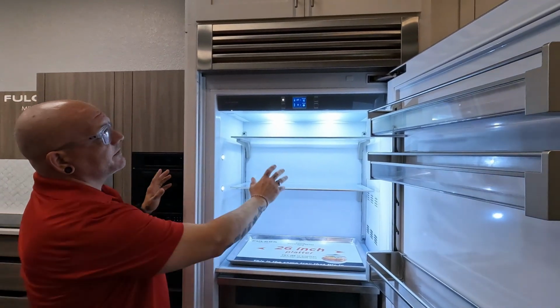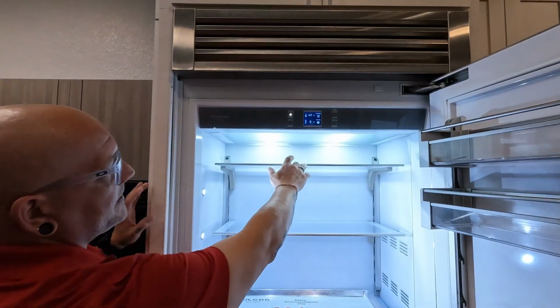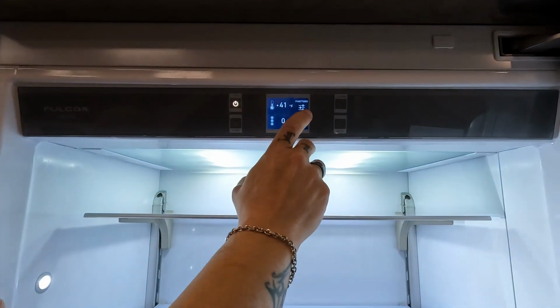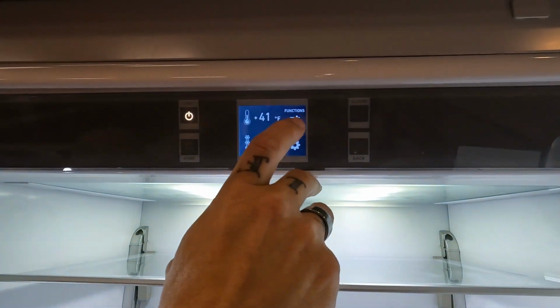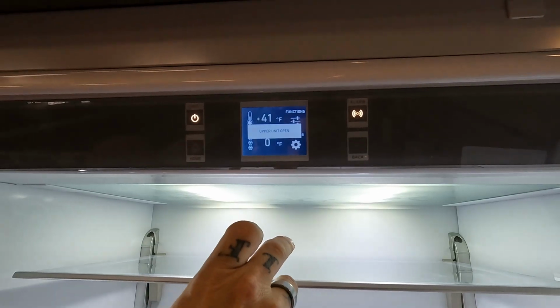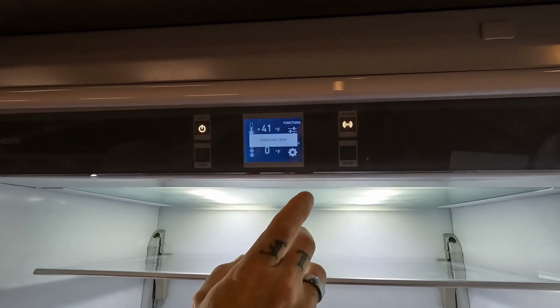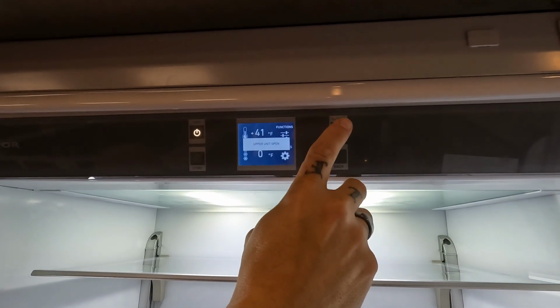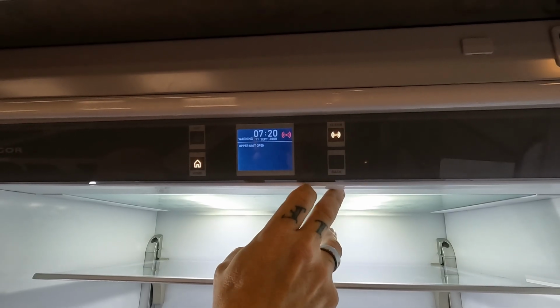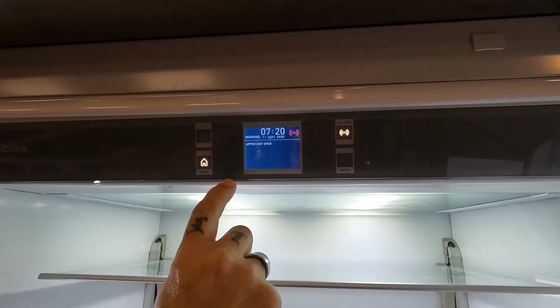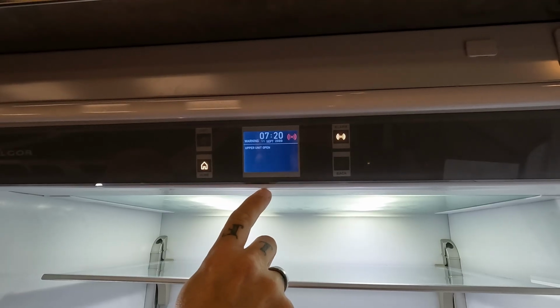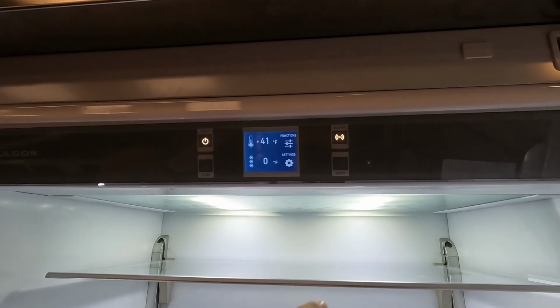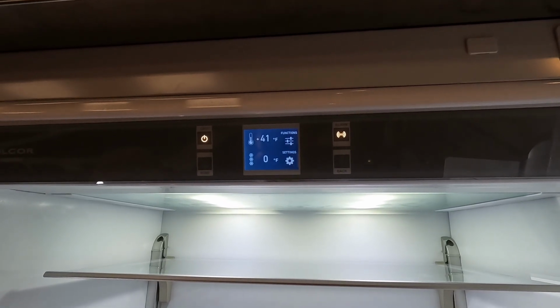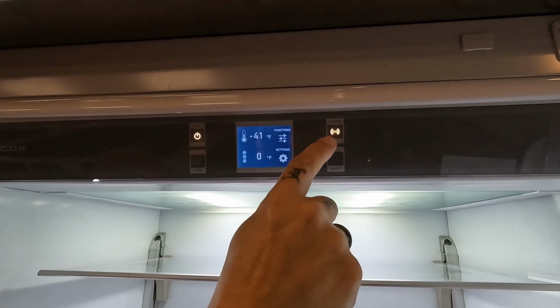Now I'll walk you through some of the settings quickly. If you see a little red triangle in the top right corner, that means there's an error code - a great example here is unit open. We had the door open for some time, so if we push this button, it tells us unit is open, warning. Pushing the button cancels the noise, but it's still illuminated because the door is still open.